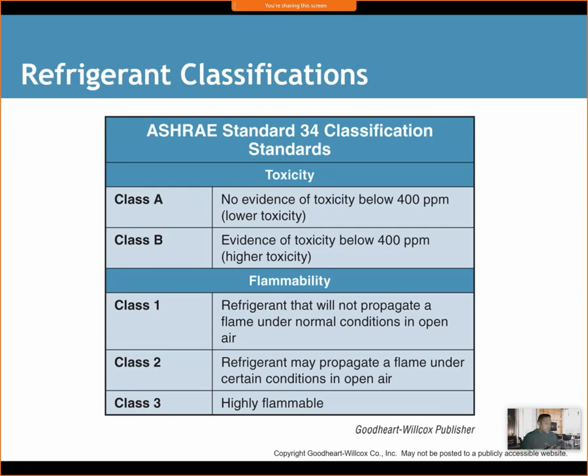Because of that, we're switching to different types of refrigerant, some like propane, where there's a potential for flammability. Over the next few years, your refrigeration equipment, like vacuum pumps and recovery machines, will have to be upgraded to handle these flammable refrigerants. Nothing to worry about now, but know that it's coming.